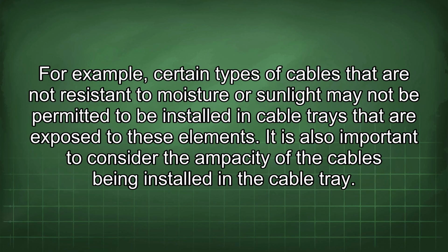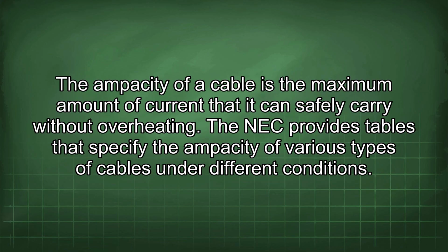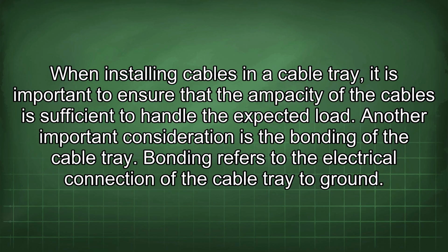For example, certain types of cables that are not resistant to moisture or sunlight may not be permitted to be installed in cable trays that are exposed to these elements. It is also important to consider the ampacity of the cables being installed in the cable tray. The ampacity of a cable is the maximum amount of current that it can safely carry without overheating. The NEC provides tables that specify the ampacity of various types of cables under different conditions. When installing cables in a cable tray, it is important to ensure that the ampacity of the cables is sufficient to handle the expected load.